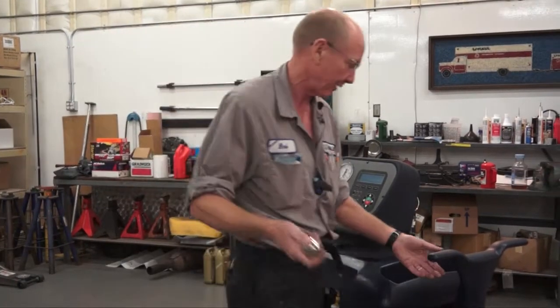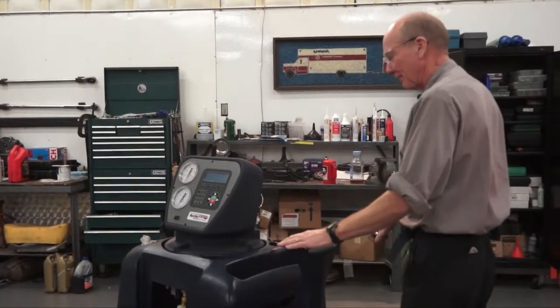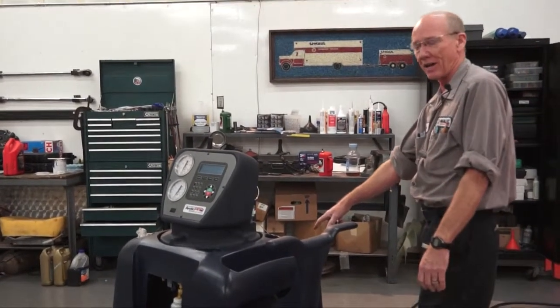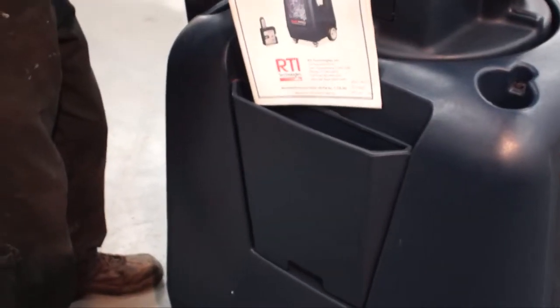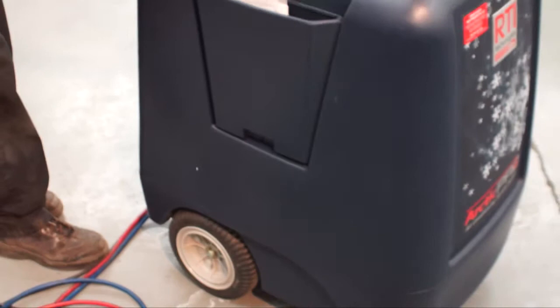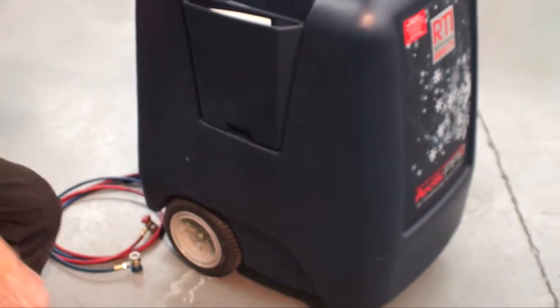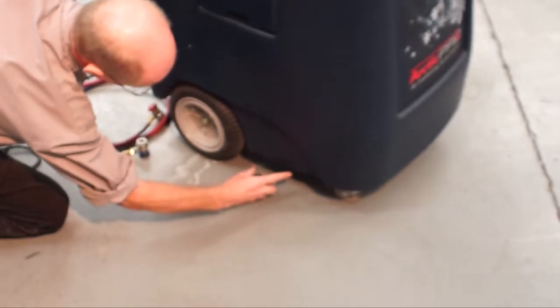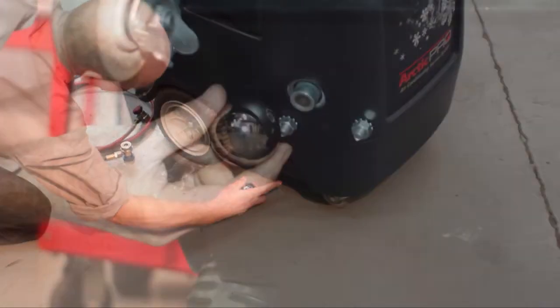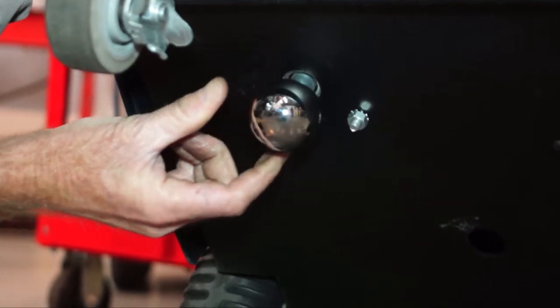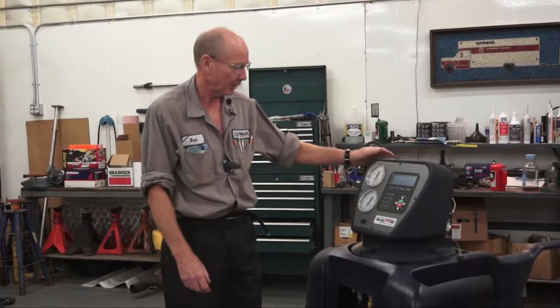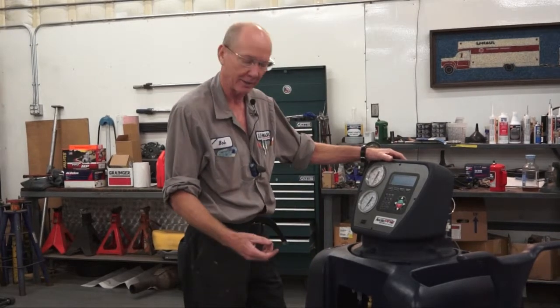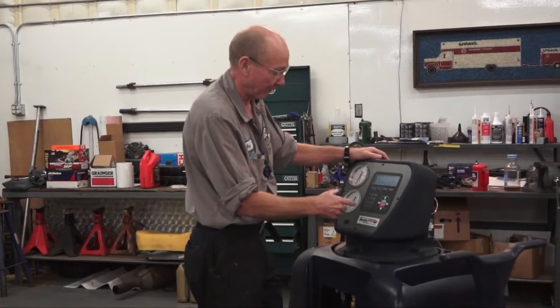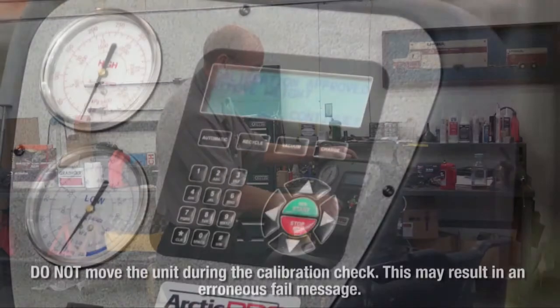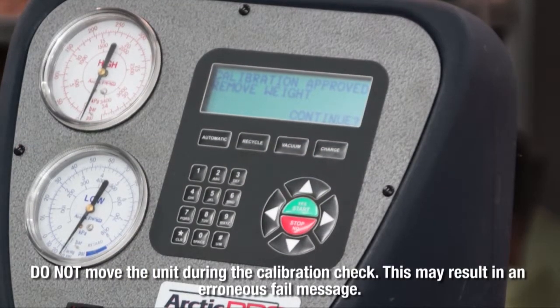Sometimes it's hard to remember where to attach that weight. What I do, it's always where your handles are. I get back behind the machine, and on the right side where the little pocket is that holds the manual, right behind that smaller wheel in the front, the little caster wheel, there's a little post that sticks down. It's a magnetic post that the ball attaches to. Okay, I attached my calibration weight to the bottom of the machine on the little magnetic post, just like the machine prompted me to do. It says continue. I'm going to hit yes. Calibration approved. Remove the weight.